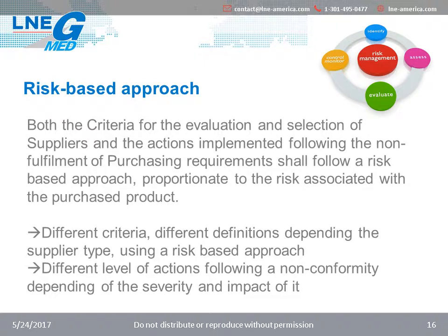It is similar for the risk-based approach that is already implemented by many organizations for the control of suppliers. However, there was nothing specific about it in the standard. In the 2016 revision, both the criteria for the evaluation and selection of suppliers and the actions implemented following the non-fulfillment of purchasing requirements shall follow a risk-based approach, proportionate to the risk associated with the purchased product. This means that companies shall consider, when appropriate, having different criteria and different definitions depending on the supplier type, as well as different levels of actions following a nonconformity depending on the severity and impact of it.